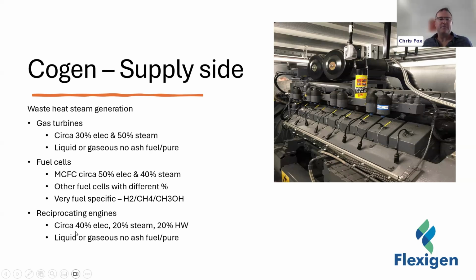Another upside is they're quite electrically efficient, typically better than the gas turbine, but the downside is their waste heat comes out in two streams: the exhaust, which you can make steam from, and the cooling of the engine itself, which can only really make hot water, up to about 95 degrees. So if you don't have a need for hot water and your site needs steam, that 20% is kind of wasted energy. And similarly to the gas turbine, they need a liquid or gaseous, low ash or low contaminant fuel.